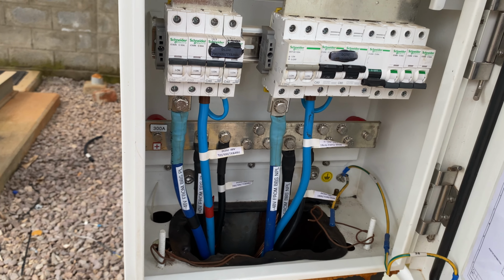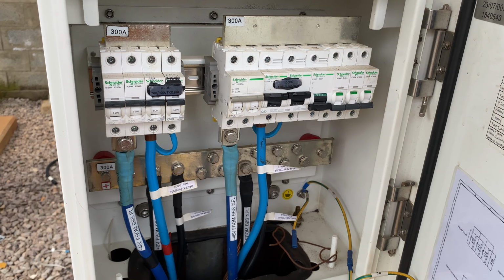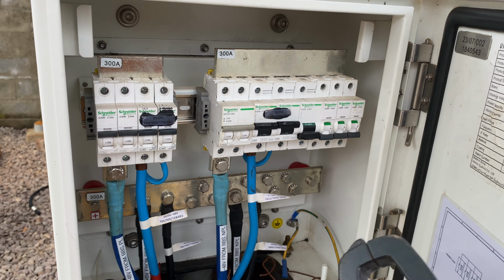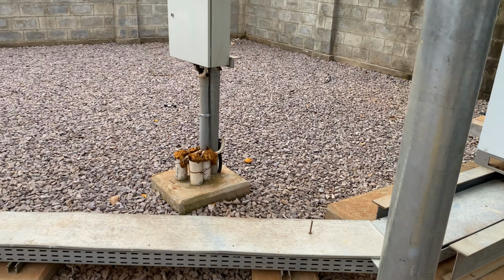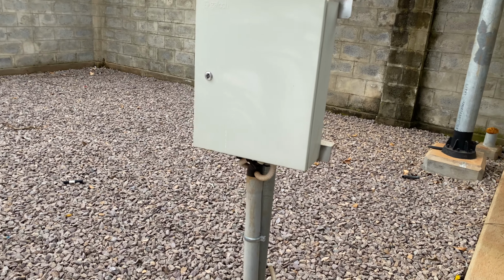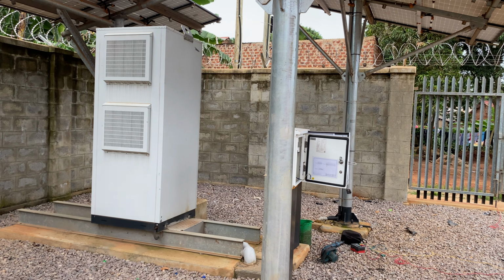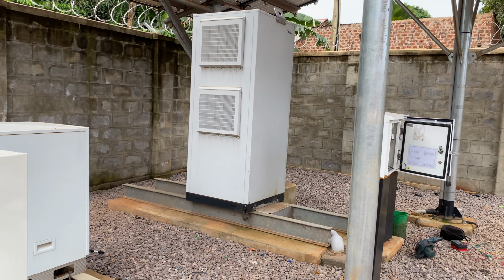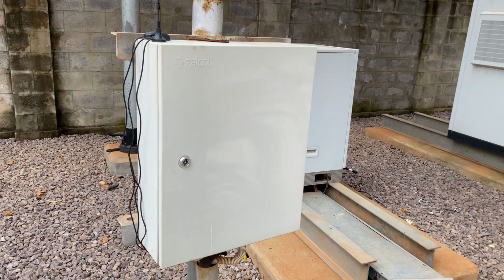Distribution board. So here, this is the DC distribution board to the clients. Maybe the client can be Airtel or MTN, and those are their servers. So this is the battery gallery. Most of these galleries are found in the rectifier cabinet, but in this case this gallery was connected separately.